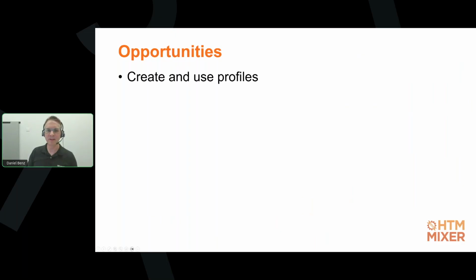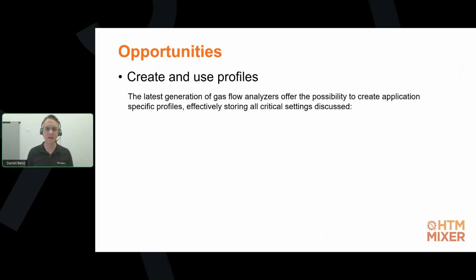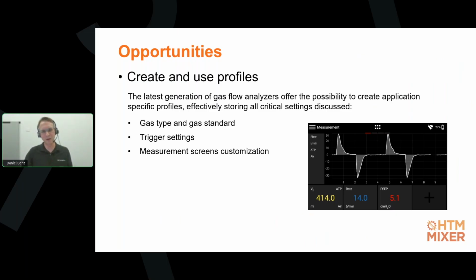So what are the opportunities posed by these challenges to set up your gas flow analyzer correctly? First of all, if your gas flow analyzer offers this feature, it's highly recommended to create and use profiles for your specific applications. On modern gas flow analyzers, you can create profiles to save all the critical settings we have discussed earlier: the gas type, gas standard, your trigger settings, and your measurement screen customizations with your units of measurement, for example. When you save them, the next time you have the same application, you can just load that profile and everything is set up correctly again. This is a really important help to minimize the risk of inappropriate settings and reading errors.